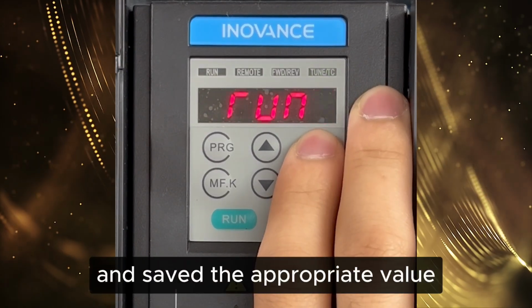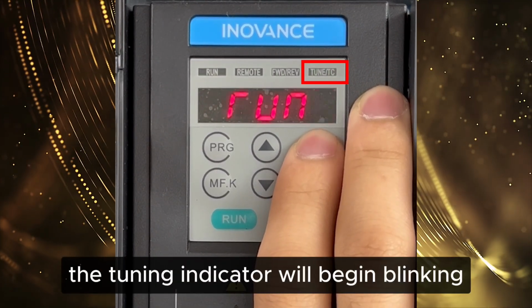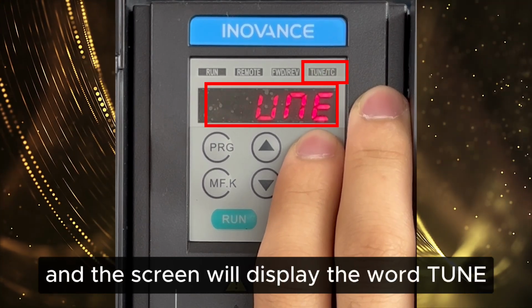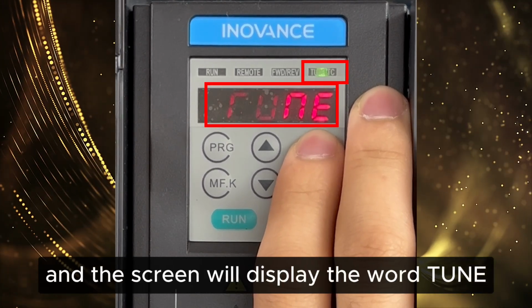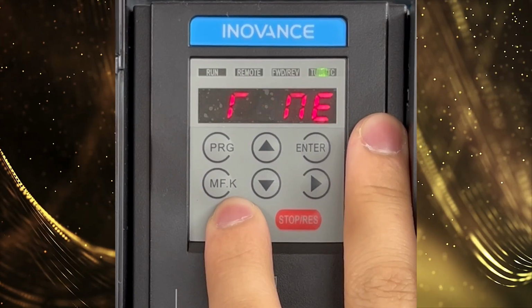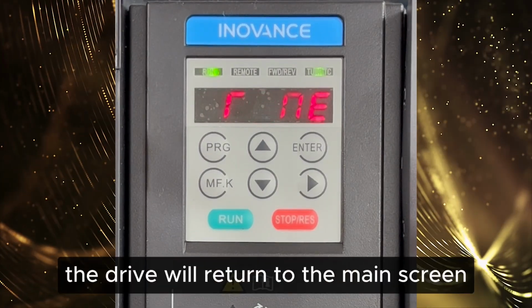Once you have entered and saved the appropriate value, the tuning indicator will begin blinking, and the screen will display the word Tune. Press and hold the Run button, and the drive will begin the auto-tuning process. This will be completed after about 4 minutes, and once finished, the drive will return to the main screen.